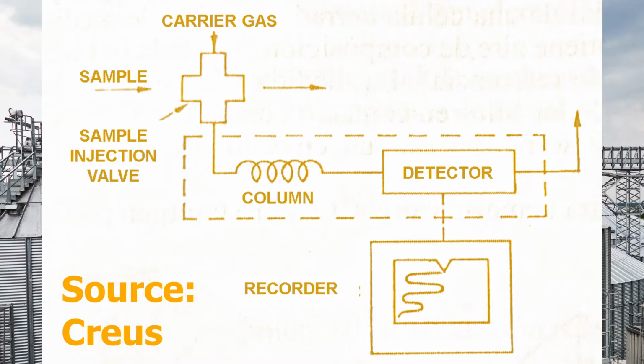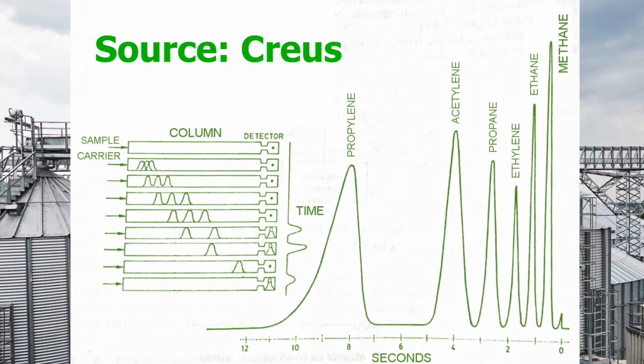An exact quantity of gas to be analyzed is injected into the column, and it absorbs each of the components differently, in such a way that they advance at different speeds, arriving one after another at the conductivity detector that compares the thermal conductivities between the carrier gas and the mixture, giving a voltage proportional to the concentration of the corresponding gas. The area of each peak indicates the amount of each component in the mixture, and the retention time identifies the type of component. The chromatograph normally requires to be installed in a clean, air-conditioned room.